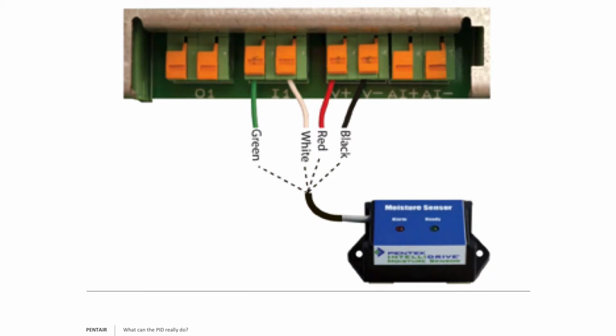And people might ask, well, does someone really try to do that? Yes, we've had customers try to do that. Because our milliamp output is limited to 20 milliamps, you can only run one trigger device off of our input 24-volt power supply. But don't worry. Remember, I told you those inputs can look for voltage 115 or 230 volt as well. So we have other options for other connections.